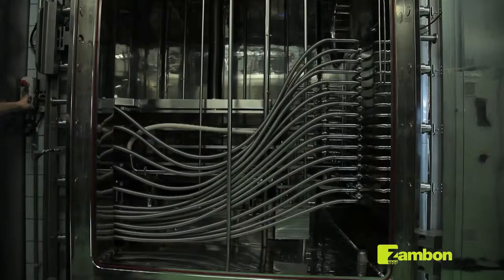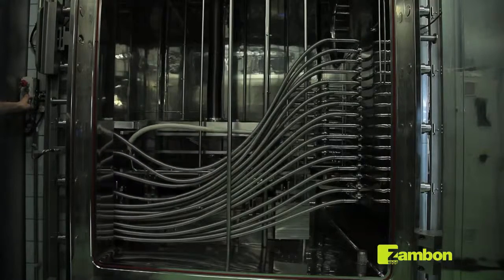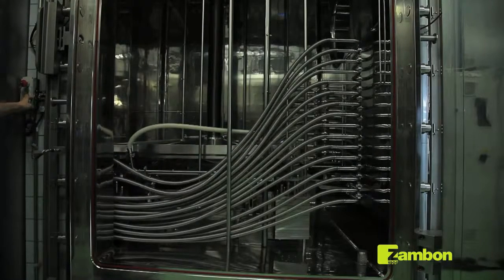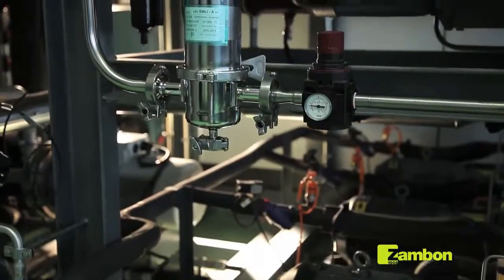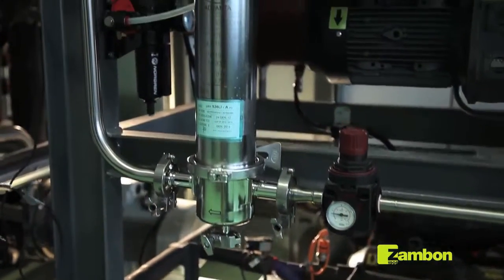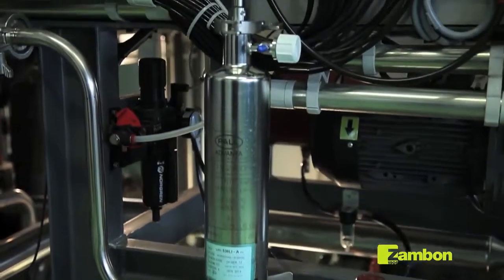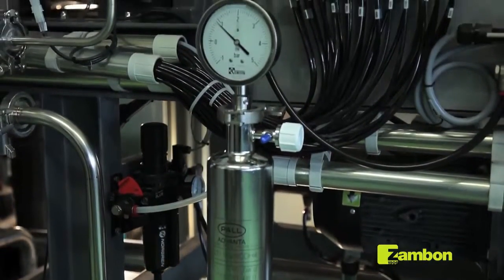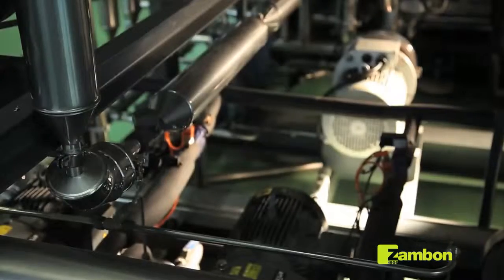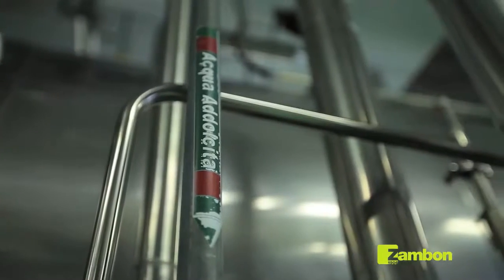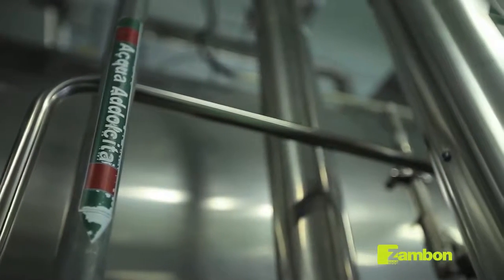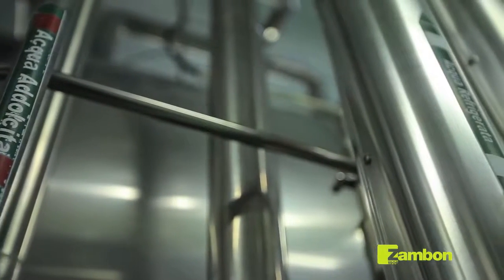After the cycle is completed, inside the lyophilizer, the shelves are lowered one by one to perform the capping operation, known as stoppering, which consists in lowering the cap completely inside the neck of the bottle. As we can see, apart from the lyophilization chamber, a lyophilizer is also composed of a vacuum pump system to reach the high vacuum necessary for the drying, and a condenser connected to the chamber through a valve, in which the water that evaporates during the lyophilization is collected.